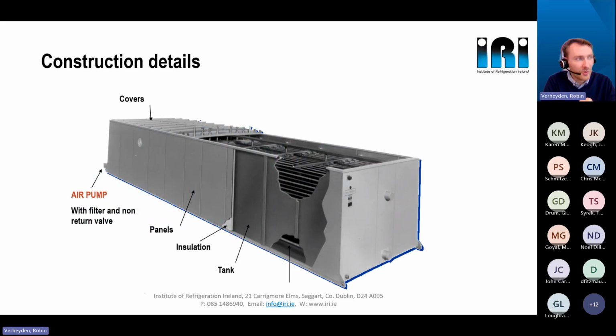So that means a typical external ice tank looks like this. A typical ice tank is a welded tank. Why? Not with a liner. The reason is that here you have additional connections because you have the loop of the water that is in contact with ice. Therefore, a weld will give better insulation or prevent leaking by passing water through different layers of panels.